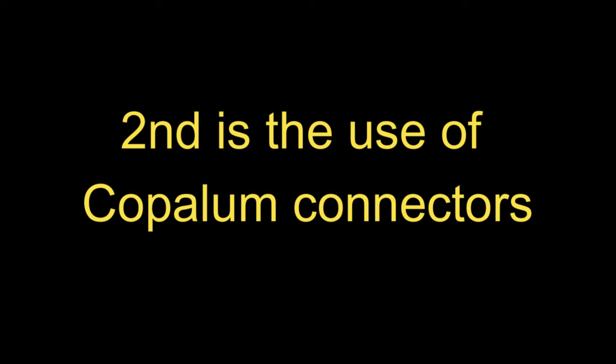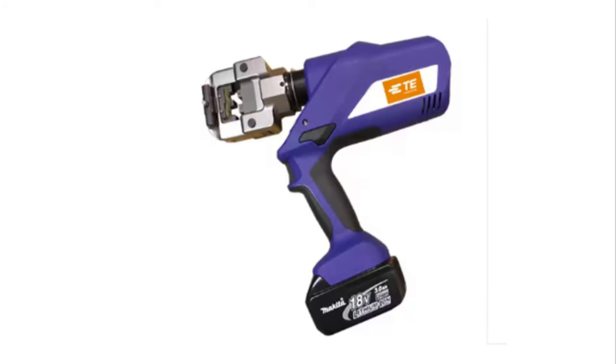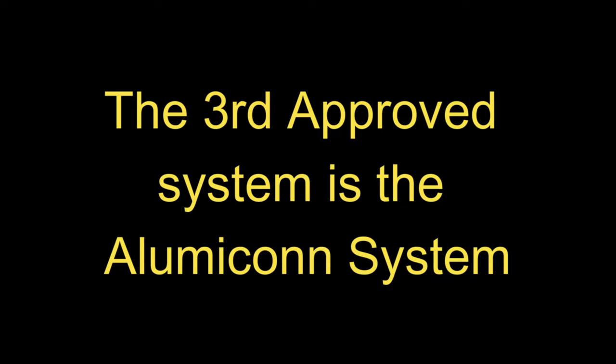The second accepted process to correct the aluminum wiring is what they call Copalum connectors. The Copalum connector is a crimp connector — you slide the aluminum wire in one side and a copper pigtail in the other side, then use a battery-powered crimper that crimps it and makes a totally correct electrical connection. The problem with the Copalum system is you have to be certified by the manufacturer, and there may not be an electrician in your area that does Copalum.